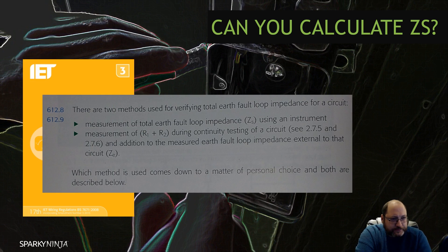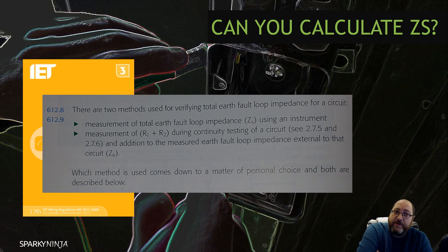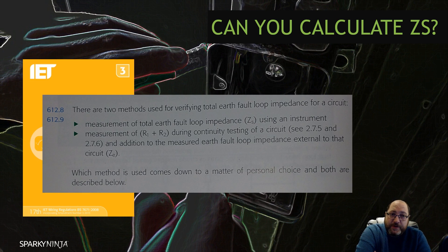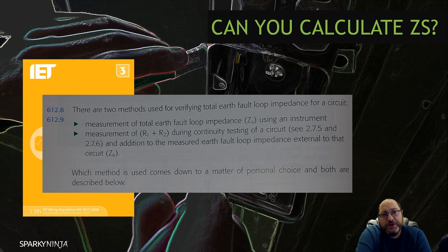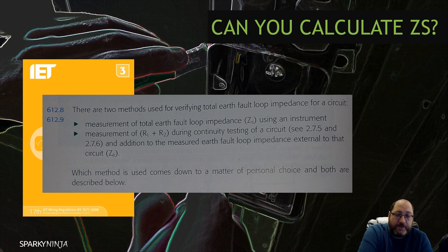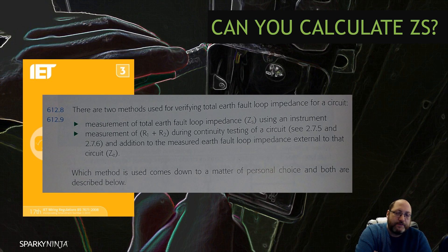Guidance Notes 3 says, in the middle of the document, that there are two methods used for verifying the total earth fault loop impedance. One is measurement of the total earth fault loop impedance using an instrument. The other is measurement of R1 plus R2 during the continuity test, and addition of the measured earth fault loop impedance external — the ZE. So it's saying ZS equals ZE plus R1 plus R2.